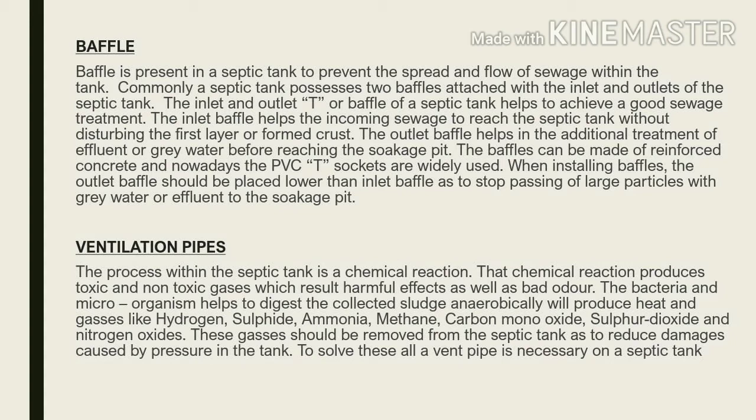It is widely used. When installing the baffle, the outlet baffle should be placed lower than the inlet baffle, so as to stop the passing of large particles with the grey water or effluent to the soakage pit.